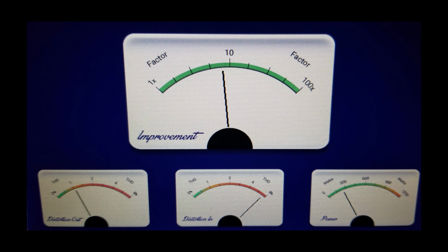time. And this is configured right now for maximum voltage regulation, so it's applying all its controls or adjustment to maintain the voltage at 120 volts output, and the rest of it is doing for harmonic distortion reduction. You can configure it so 100% or the larger percentage is for harmonic distortion reduction, and the rest of it would be for voltage regulation, so that would allow the voltage to deviate slightly from your set point rather than keeping the voltage at a fixed 120 volts. But it would also offer a higher reduction in the harmonic distortion.